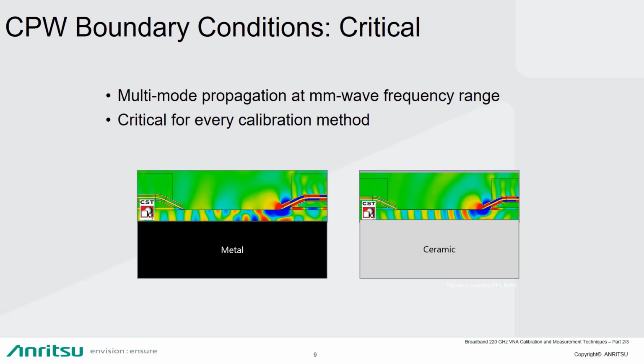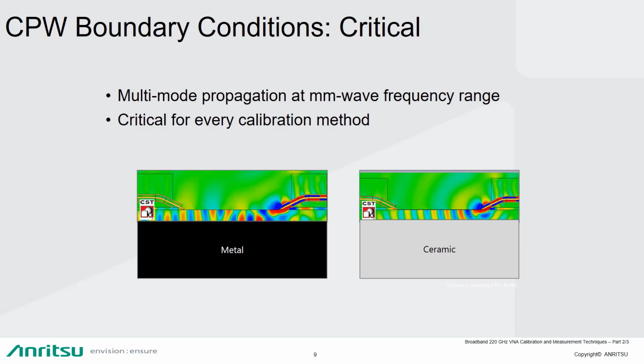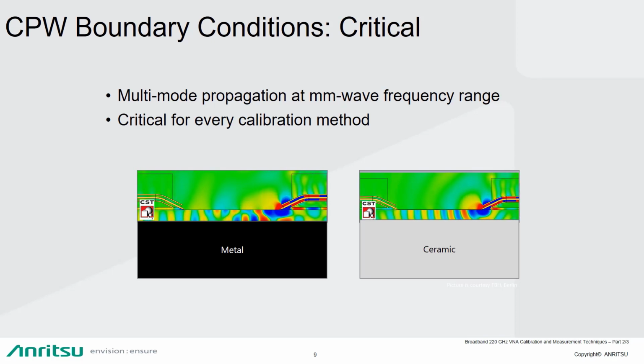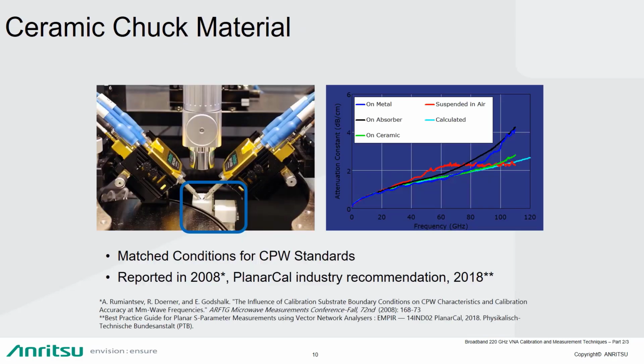So this situation is critical for any calibration method. We have to make sure that the measurement of all calibration standards are conducted at a single quasi-TEM propagation mode. So the right-hand picture is using a ceramic chuck, and it demonstrates this condition. Such an optimized condition can be achieved if the system auxiliary chucks are thick and are made of ceramic. The chuck dielectric constant has to be matched with the dielectric constant of the calibration substrate.